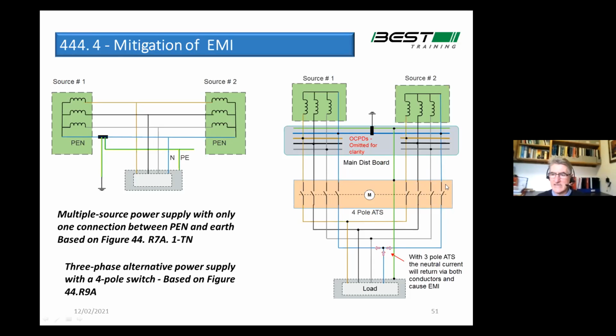Whether it actually is that hazardous or not, I don't really know. It's a very specialized field, but I would be inclined to say you should be following the guidance. If it's recommended to use 4-pole, you should be really using them. And particularly if there is an EMI issue later on, you can't really sign off and say you've complied with the wiring rules if you've gone off and used a 3-pole.